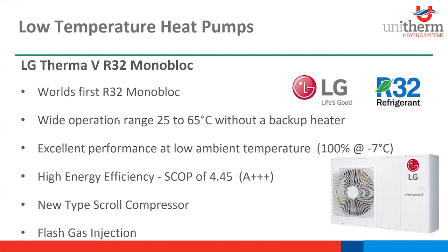Now for NZEB buildings, the weather compensation floor temperature is typically 32 to 38 degrees. Running at a lower temperature gives minimal input with the highest COP value, so the highest coefficient of performance. The new type scroll compressor varies running frequency with precise control. The lower the required flow temperature, the lower the frequency, and the lower the bills.